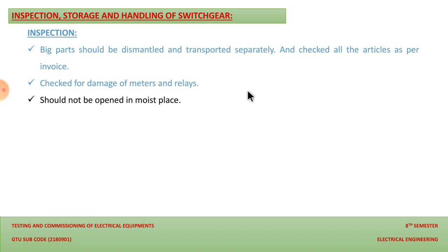Then you should not open the circuit breaker, or we can say switchgear, in a moist place. We have the quenching mechanism, or we can say movable parts, in the switchgear. So we should avoid opening the switchgear in a moist atmosphere, because if we open the switchgear in a moist atmosphere, it will absorb the moisture of the surrounding atmosphere, and there will be chances of corrosion in the moving parts. So it should not be opened in a moist place. We should keep this point in mind while inspecting the switchgear, while we receive the switchgear at the consumer premises.